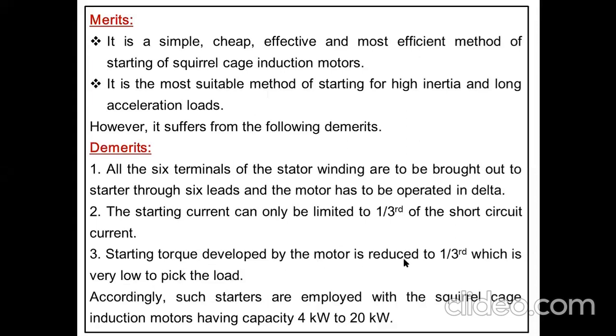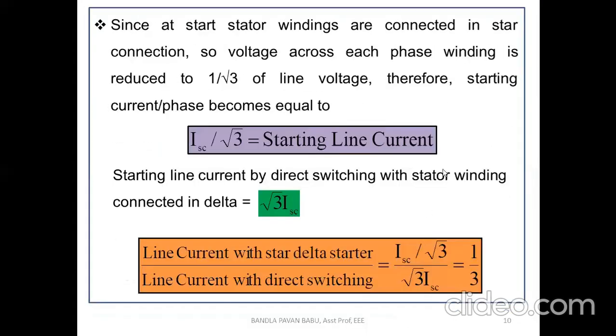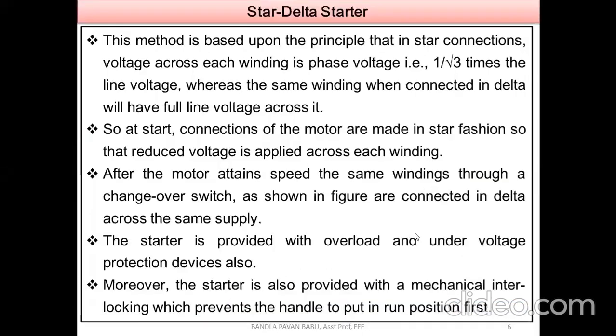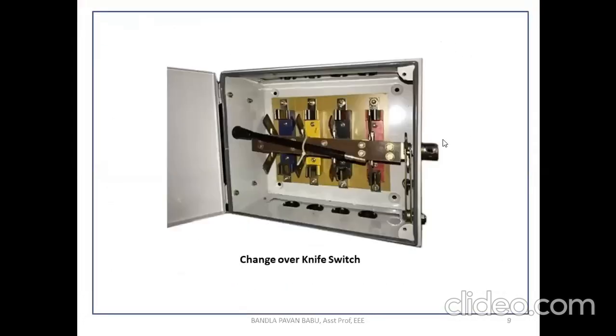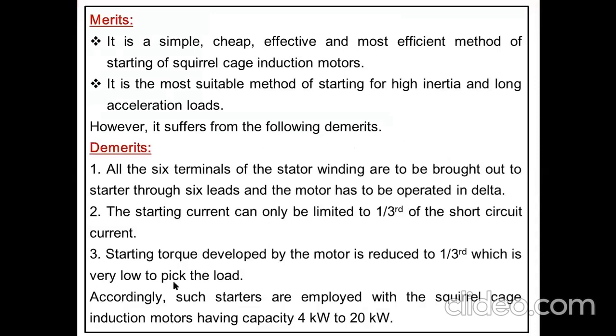Next, the starting torque developed by the motor is reduced to 1/3, which is very low to pick up the load. As I said, the starting current is limited here, which will reflect on the voltage also. Because of this voltage only, the current is limited. Look here, it is VL by root 3, 1 by root 3 times the line voltage. So the voltage is reduced, and obviously there is an effect on the torque, because T is proportional to V square. Accordingly, such starters are employed with squirrel cage induction motors having capacity 4 kilowatts to 20 kilowatts. So between these ranges of machine, we can use this method.